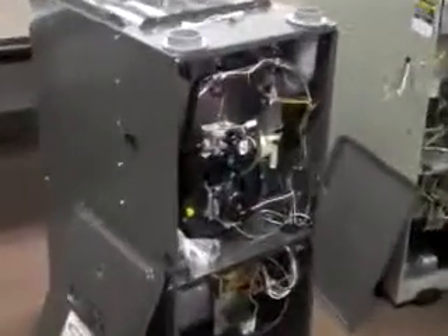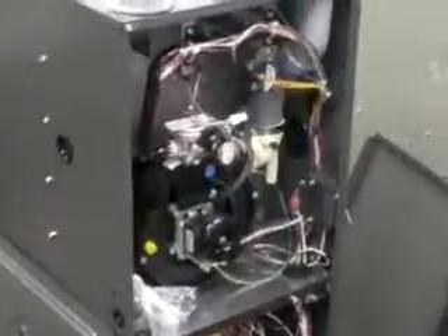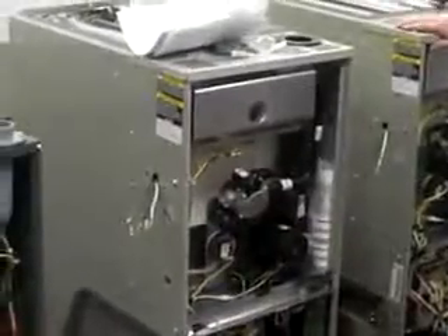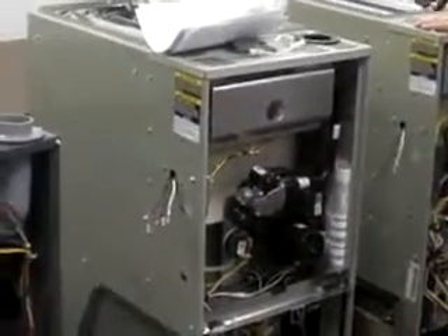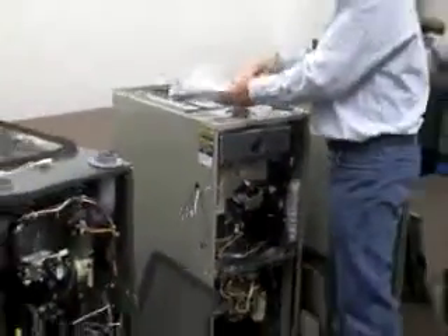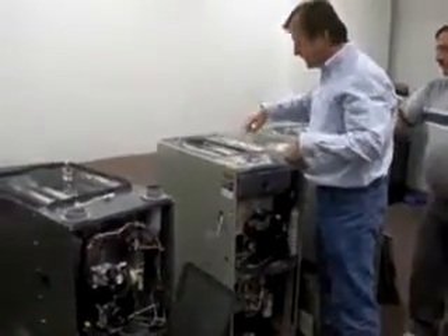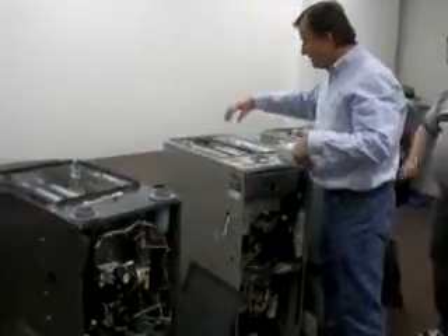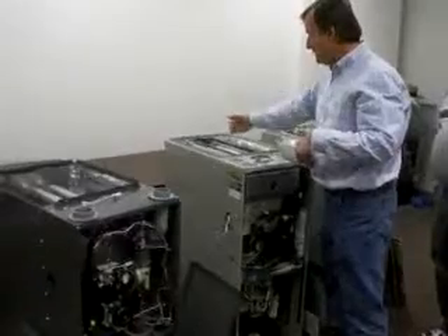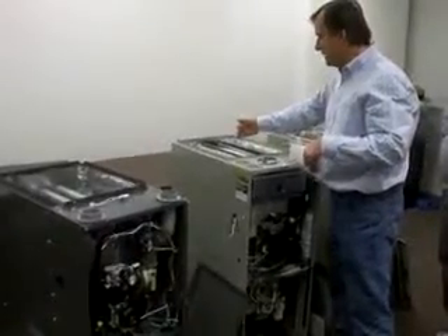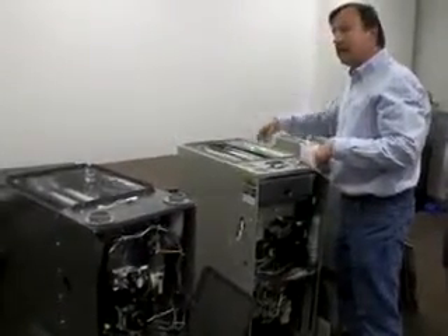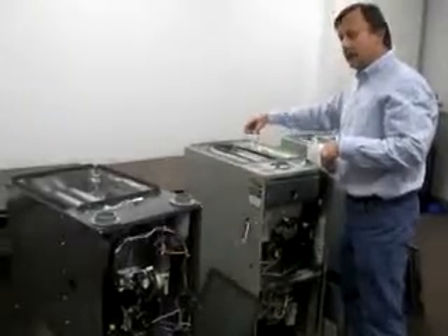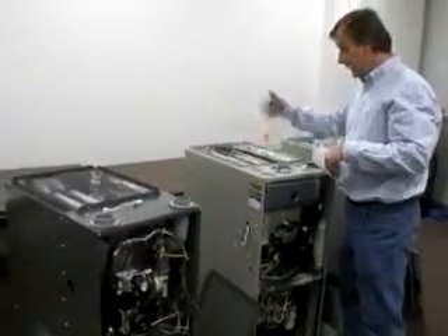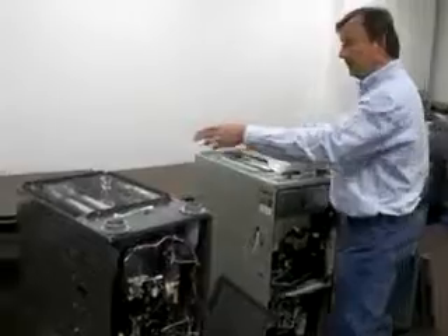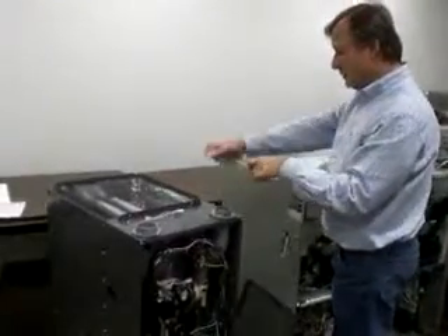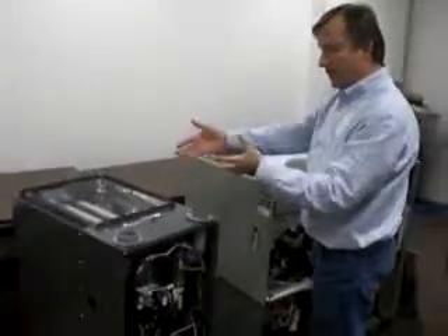Trane uses what's called a low energy fan, okay? A couple of reasons. First of all, we don't need the velocity, we don't need the volume to pull the products of combustion through our heat exchangers, because our heat exchangers are much larger, they have much more surface area to exchange the heat onto the primary heat exchanger, and the gases can spend a little bit longer time in there in order to make it more efficient. Tubular heat exchanger, if the gases spent too long a time in there, it would burn it up.